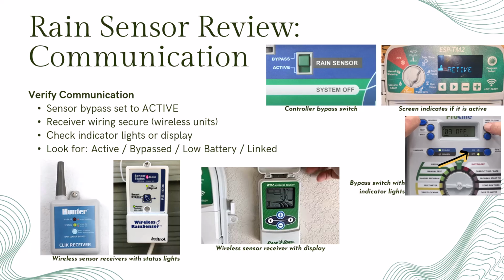After the physical check, I verify that the rain sensor is actually communicating with the controller. First, I confirm the bypass is not set to off or bypass. If the sensor is bypassed, the controller will water even after rainfall, which defeats the purpose of having the device.